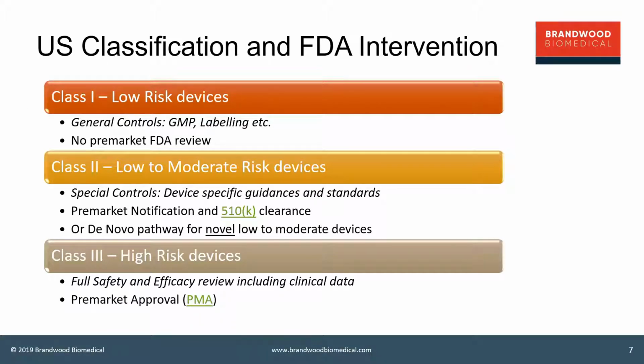So if we now focus on the US model, here we've presented in a really summarized form the three types of classes that we'll find for medical devices and IVDs. There are three classes, going from the lowest risk and moving to low and moderate risk and then high risk devices. The level of intervention from FDA obviously grows, as we explained before, with those types of devices. So low-risk devices do not incur any pre-market FDA reviews.